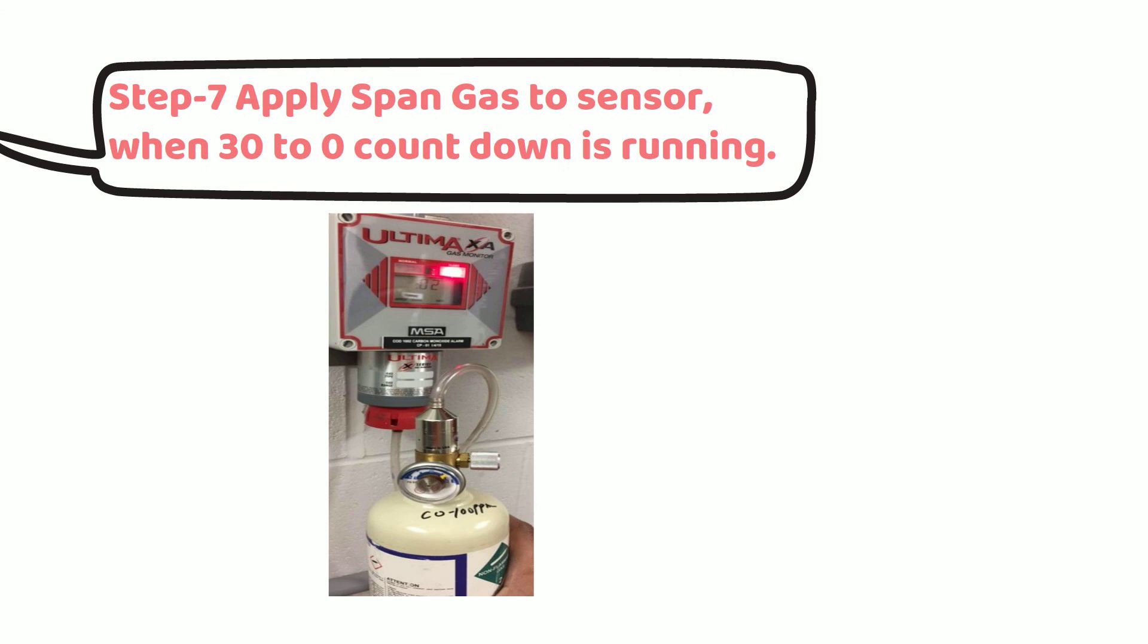For example, if span is set for 100 parts per million of carbon monoxide, then you have to apply 100 parts per million gas to sensor.